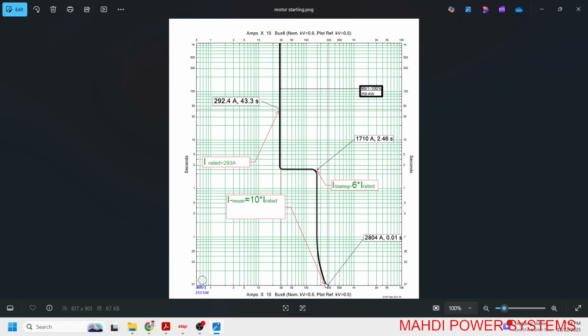The motor started here. At the moment the motor is energized, at this point, we see a very high current spike called inrush current. The current can reach up to 10 times the rated current, but lasts only a short time, typically around 20 milliseconds. 20 milliseconds for inrush current. And then the starting current can reach up to 6 times the rated current. Here we have I starting, 6 times I rated. It takes 2.5 seconds for these motors.